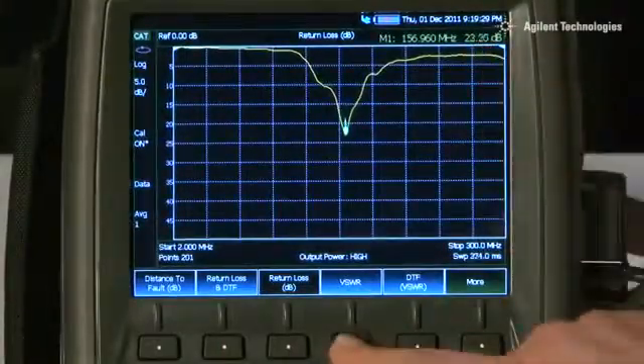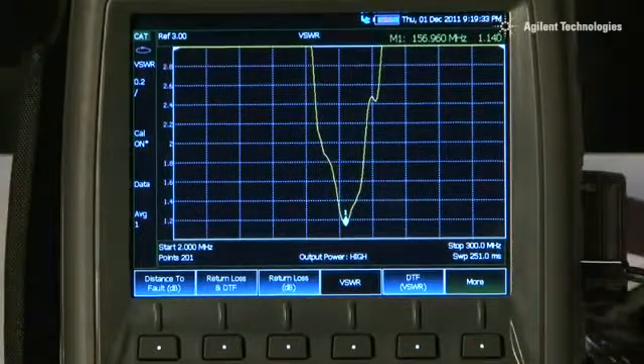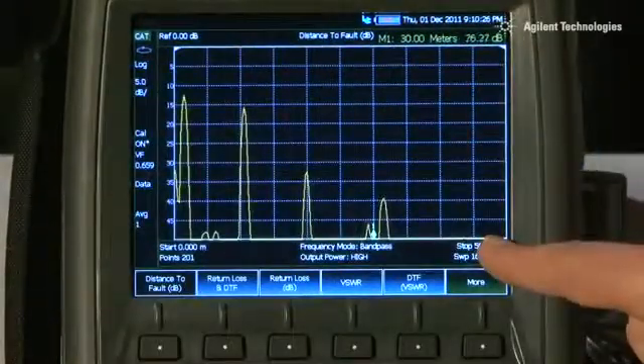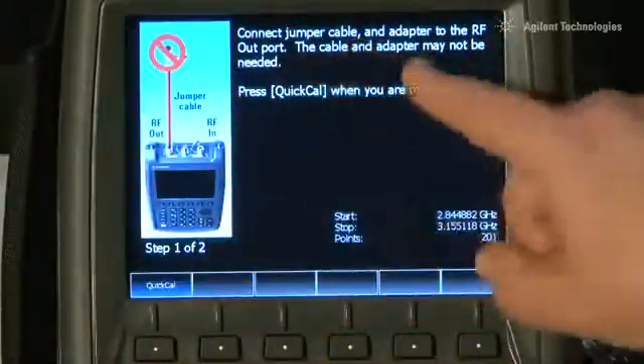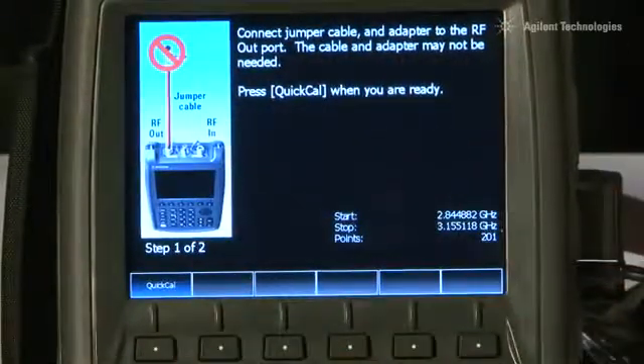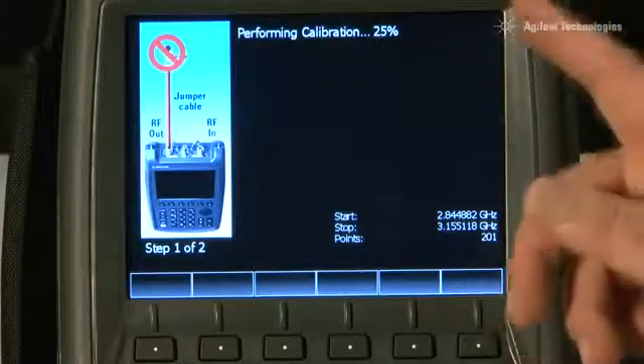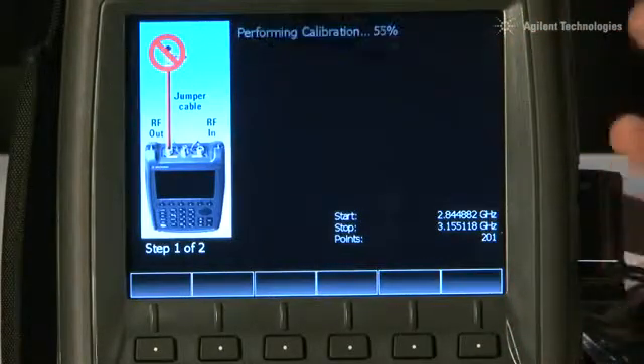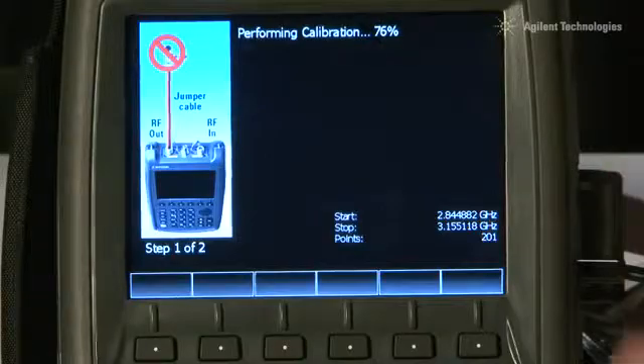It measures return loss, VSWR, cable loss and distance to fault and we can even make many of these measurements simultaneously. Best of all, the built-in quick-cal capability means that we can calibrate the instrument when out on site without the need for an external open short load calibration kit.